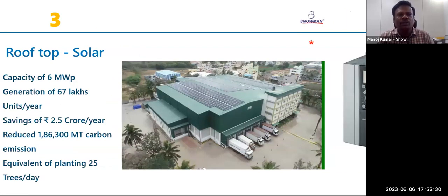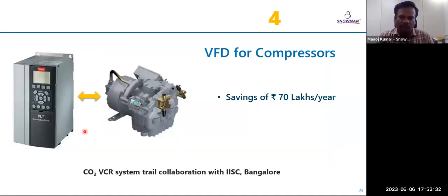Later we installed variable frequency drives for these compressors. Without a VFD, the compressor simply works on or off. With a VFD, it makes sure the compressor runs only wherever required, and the speed of the compressor is controlled based on the individual compressor load. By the VFD, we are saving 70 lakhs per year.